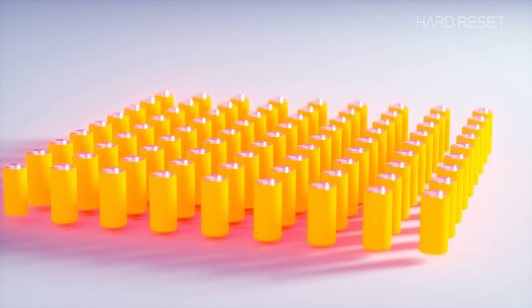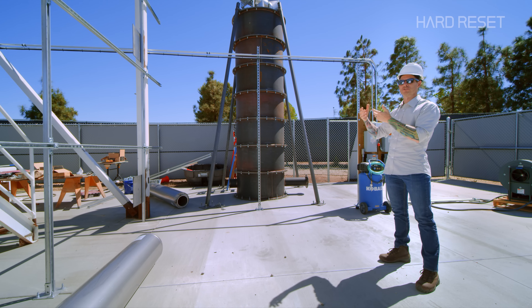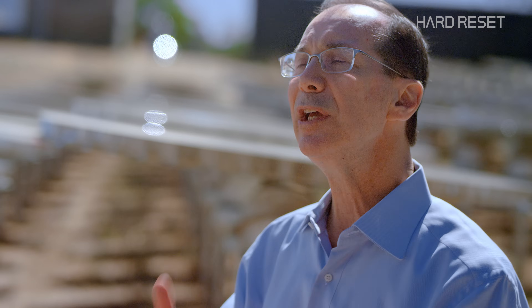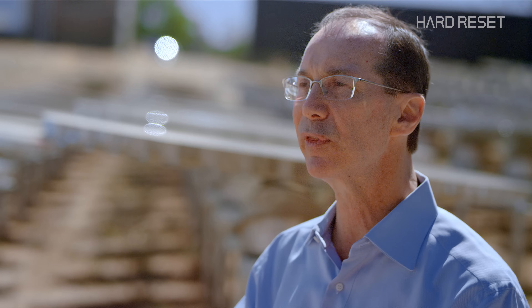That heat is important because solar energy needs to be used immediately or stored somehow. Batteries are expensive and problematic, but you know what's cheap and safe? Just normal rocks. We take that high temperature and bring it down into a rock bed — we literally heat rocks to 1,000 degrees centigrade. The temperatures are so high the metal actually can't take it, so we put the insulation on the inside to protect the steel. If you heat rocks to 1,000 degrees centigrade with photons, they now stay hot even after the sun goes down. Those rocks are in an insulated tank, like a thermos, and they'll stay hot for a week — acting as batteries, storing energy that can be used to generate power 24 hours a day. It allows us to power things that need to run around the clock, and civilization does run around the clock.